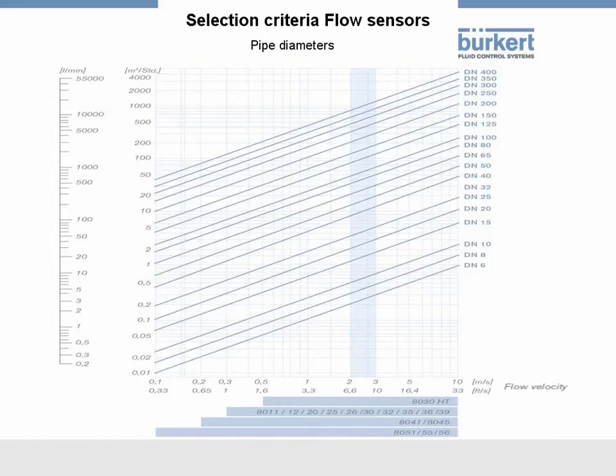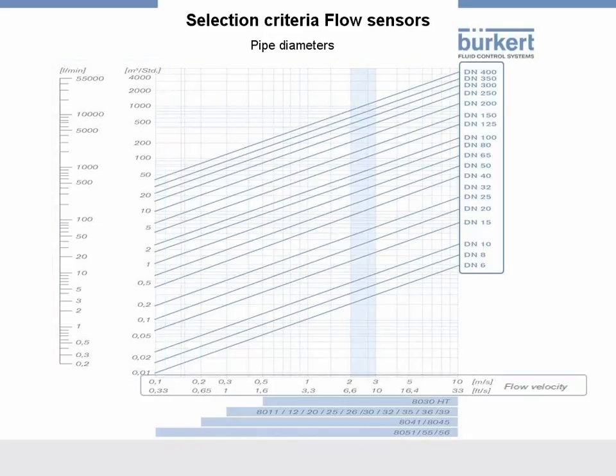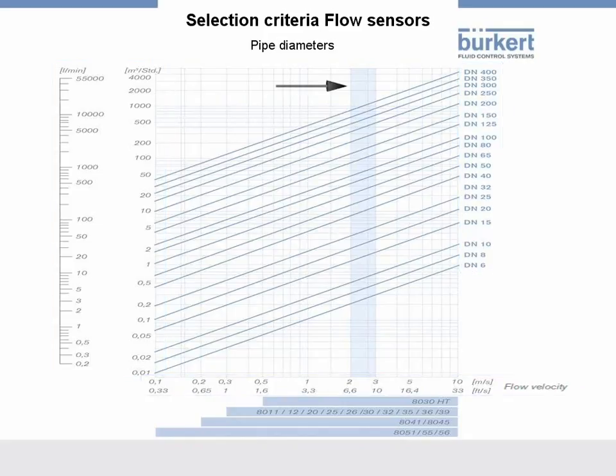The diagram for selection of the diameter allows the user to determine the required diameter based on his application conditions, the flow speed, and corresponding flow rate. One can see the possible flow rate for a given diameter based on the flow speed. Its optimal range of 2 to 3 meters per second is marked by the blue vertical bar. If a user knows the minimum and maximum quantity to be measured, he can use the diagram to find the suitable diameter for the pipeline.